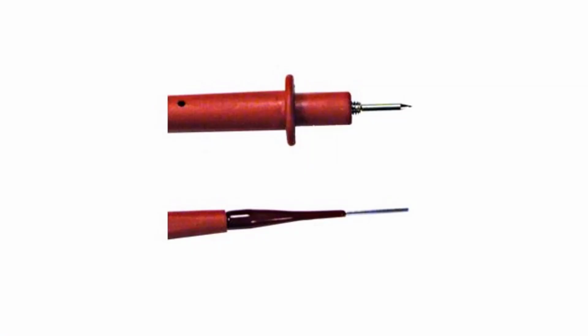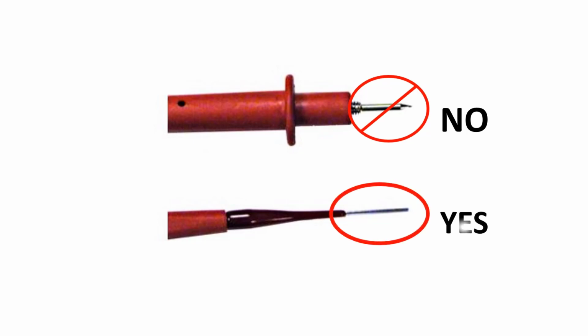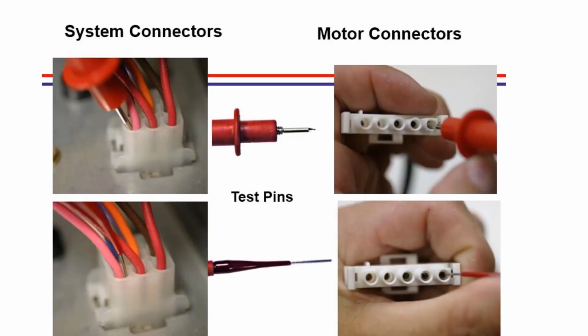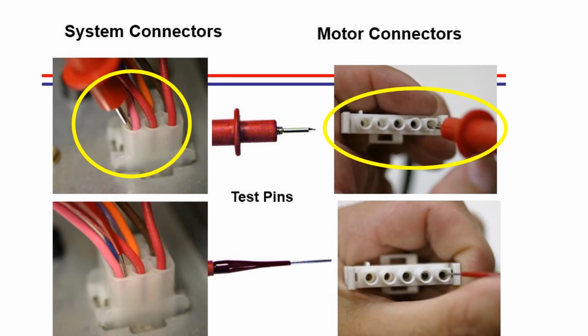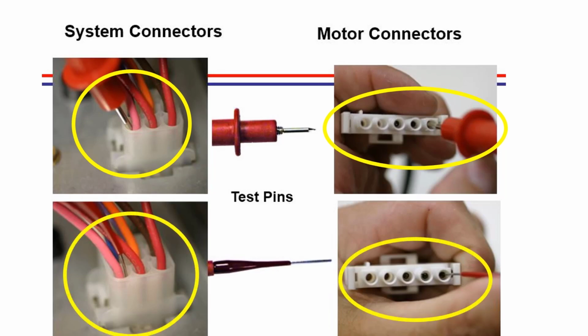In preparing to check the communication wires, you need to make sure that instead of having the large fat probes on your meter, you need the skinny ones that'll be able to get into the plug easily and make readings without damaging the plugs and the contacts. With the larger probes, it is easy to damage the plugs and the contacts, and sometimes it's hard to get the fat probe into the plug to make a connection to make a reading. This is why the skinny test probes are a lot more useful in getting into the plug and not making damage to the plug or the contacts.